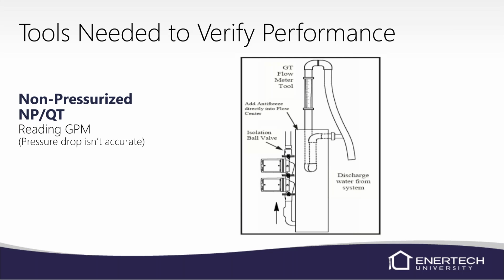If you guys have worked on boilers or any water systems with a sight glass in it, you know that over time, and it really doesn't take too long, it's going to get cloudy or brown, and you're not going to be able to see it anyway. So it doesn't have to stay in. Once you set your water flow, nothing should change in the system. So once you set your water flow, you shouldn't have to reset it.